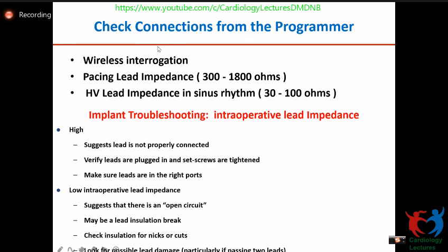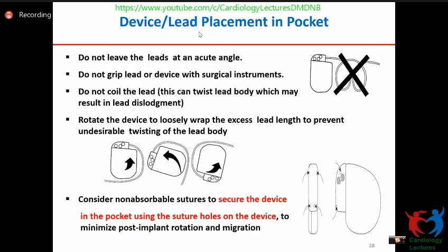You can also check connections from the programmer through the impedance. If the patient has high impedance, that suggests it's not properly connected. If low impedance, that may suggest there's an open circuit.